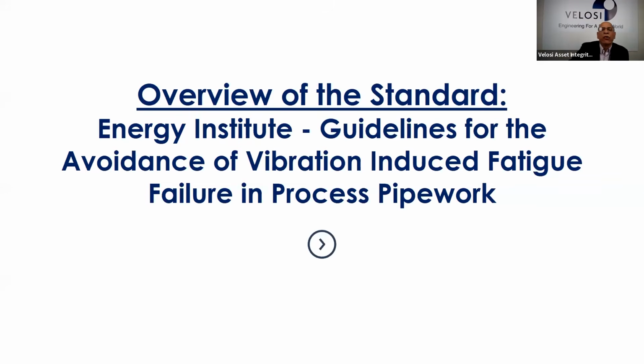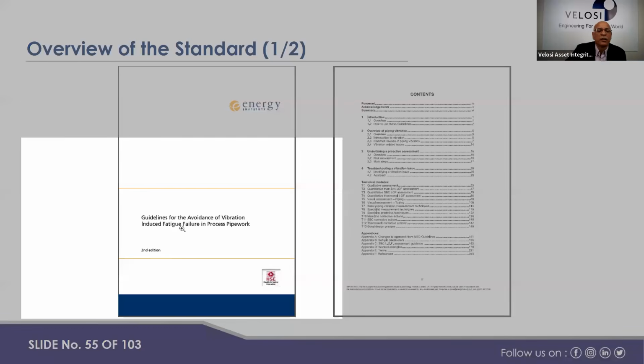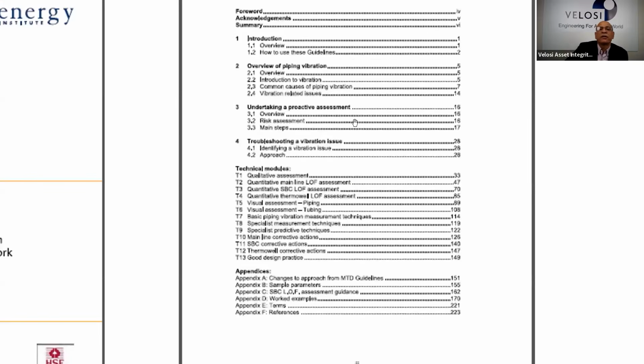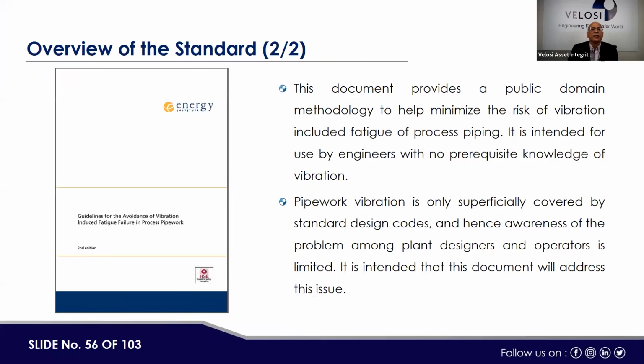Now, we have completed the overview of the standard, which is the Energy Institute guideline for the avoidance of vibration-induced fatigue failure in process pipework. The topics covered under this standard are an overview of piping vibration, including an introduction to vibration, common causes of piping vibration and vibration-related issues, then undertaking the proactive assessment, including an overview, risk assessment and main steps, then troubleshooting a vibration issue, then technical modules of various kinds. So this standard is very useful if you wish to refer to it to control piping vibration-related integrity issues.